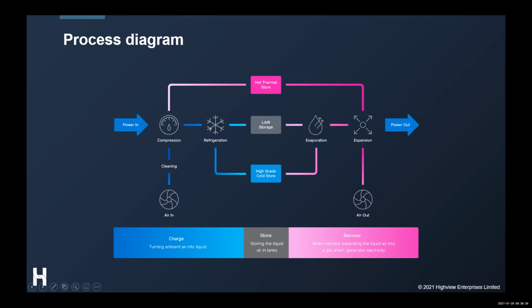Our liquefier system is loosely based on the Claude cycle, which means that a portion of our refrigeration is provided by a cryogenic expander. So during the cooling process, we take off a portion of our gas, which is again at 60 bar. We expand it to in and around 15 to 20 bar, and we can produce some work by this, which we can use to offset the loads on the compressors. This is hooked up by an asynchronous generator. The cryogenic expander is a single stage radial turbine, and its primary function is to provide this refrigeration effect. So the gas is cooled down to about minus 160 degrees Celsius or so, and it's run against the process gas in the main heat exchanger, and this provides about 50% of the cooling requirement.